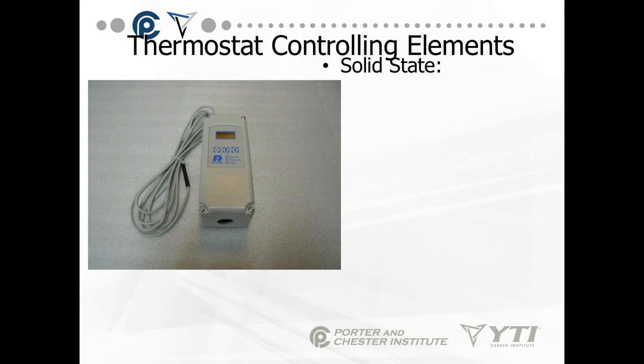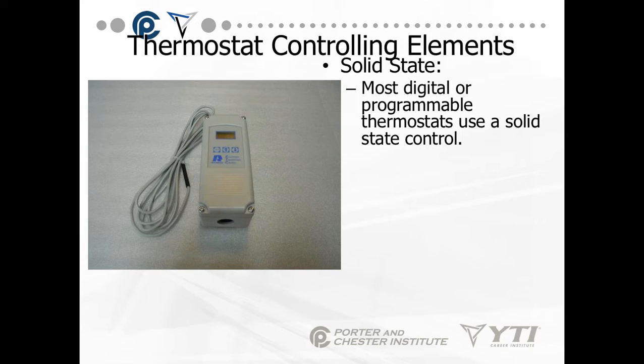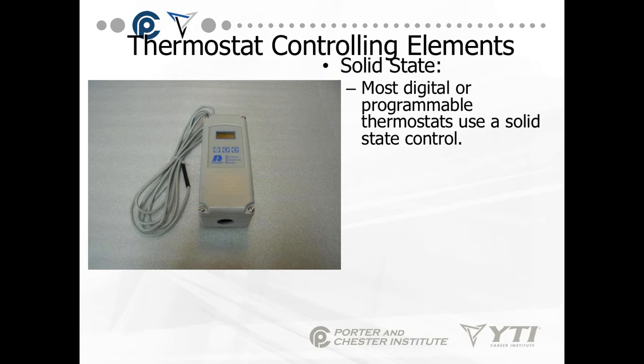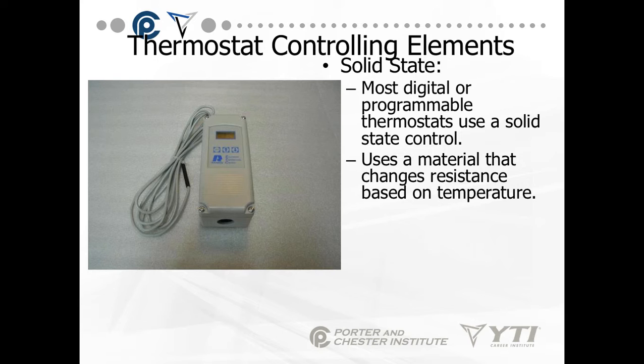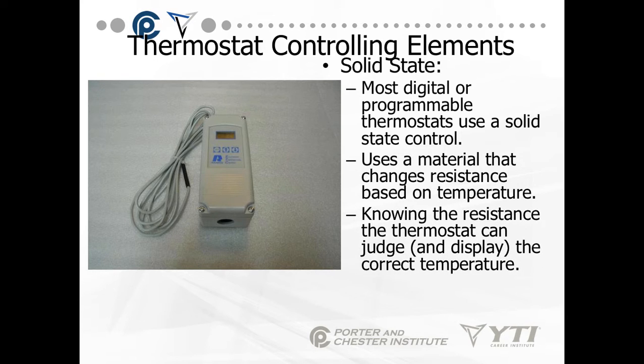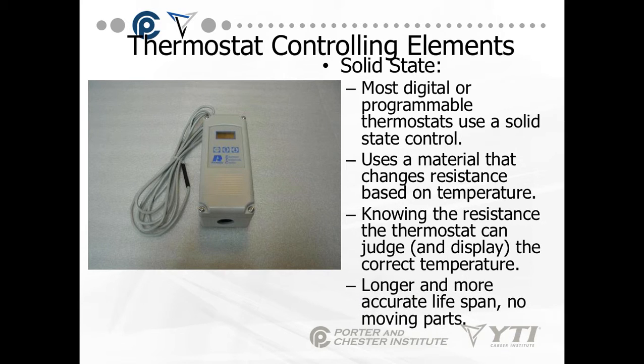The final type of controlling element is the solid state, and that's where everything is going — the other thermostats are slowly being replaced. Solid state is used in most digital or programmable thermostats. It uses a material that changes resistance based on temperature; knowing the resistance, the thermostat can judge and display the correct temperature. It has a longer and more accurate lifespan, there are no moving parts, and we can connect them to computers, alarms, and other output mechanisms.